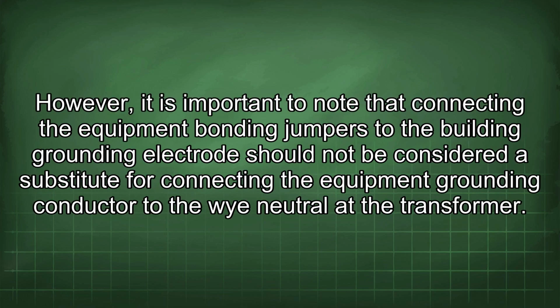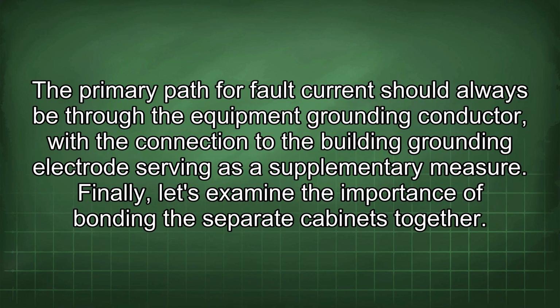However, it is important to note that connecting the equipment bonding jumpers to the building grounding electrode should not be considered a substitute for connecting the equipment grounding conductor to the Y neutral at the transformer. The primary path for fault current should always be through the equipment grounding conductor, with the connection to the building grounding electrode serving as a supplementary measure.